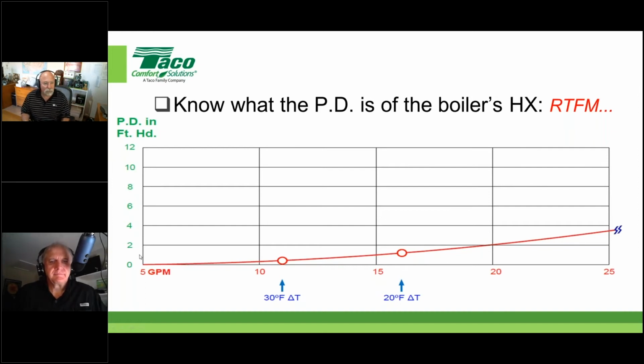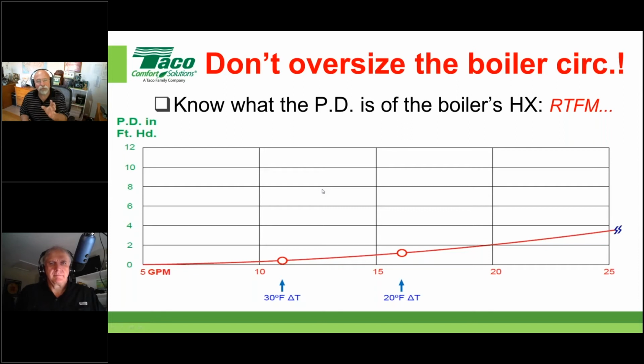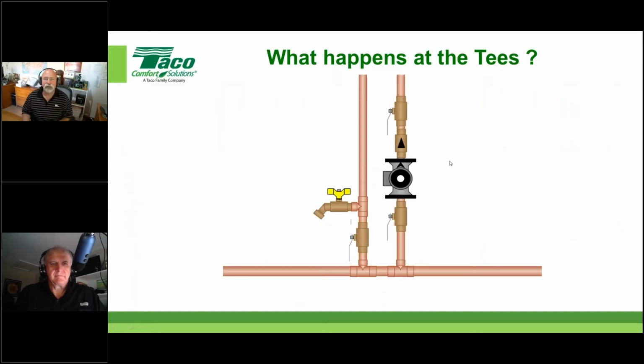You have to know that, and that's what these little curves look like. In this case, this one points out what you would be at a 30-degree delta T. This shows what you'd be at a 20, etc. So just know that. What this will do is keep you from oversizing that boiler circulator, which we're going to keep pounding away at you is a bad thing.